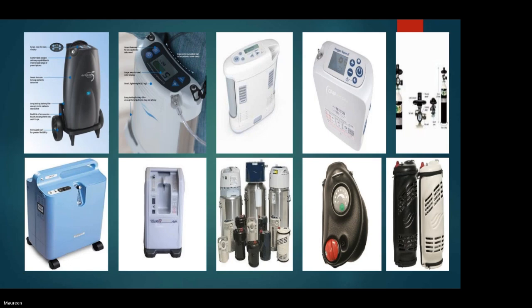And the other thing you've got to be mindful about these machines is that usually the companies give about 30 foot of extension tubing with them, and then your 6 foot nasal prongs are attached onto that, or your connection tubing for your mask. You have to be mindful of, if you want to extend the length of that tubing, that will impact on the flow of oxygen that actually you receive through the nasal prongs. Okay, so that's an important point.